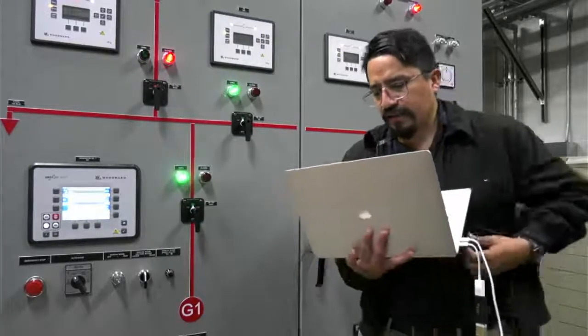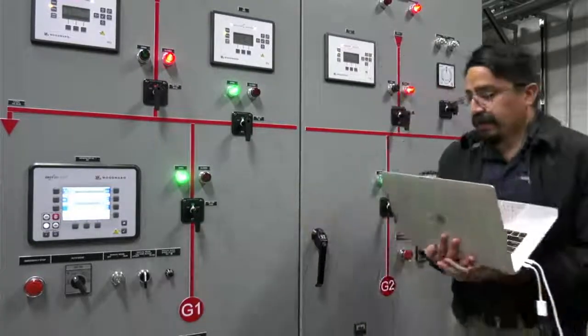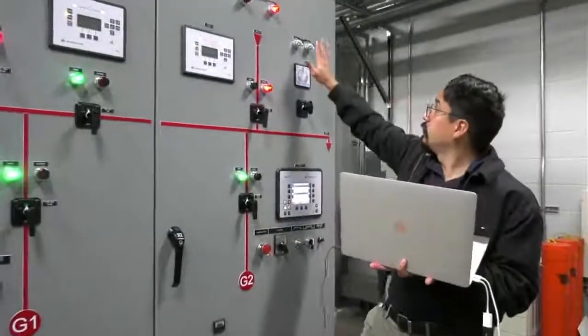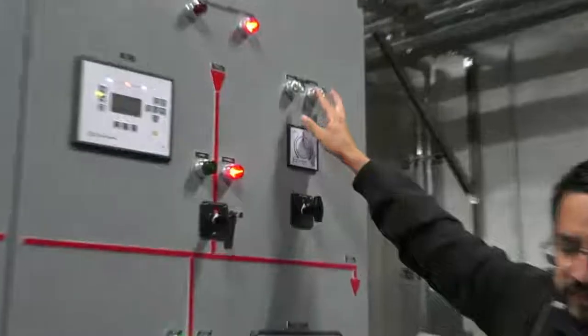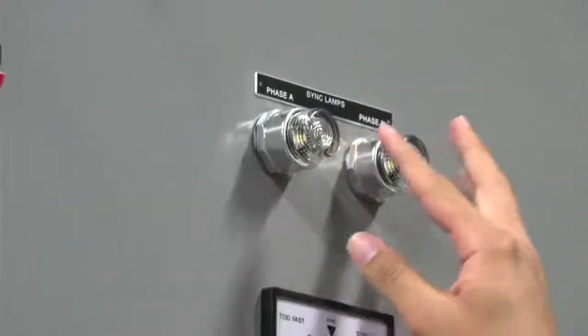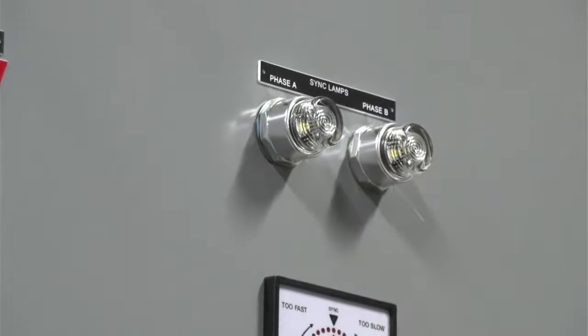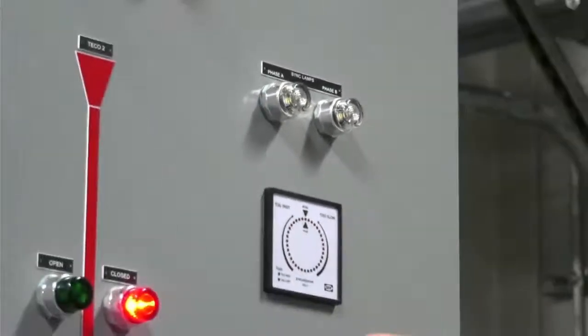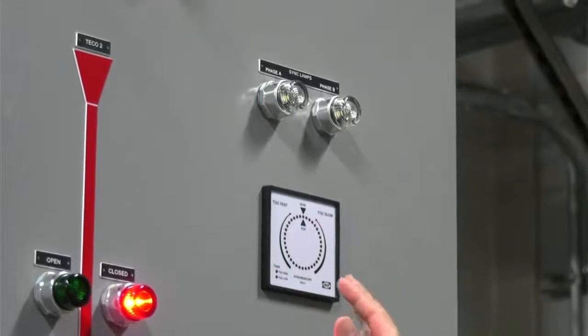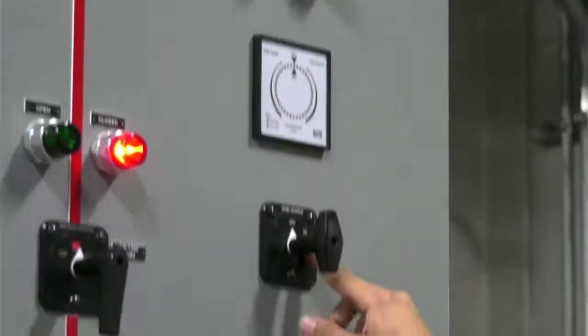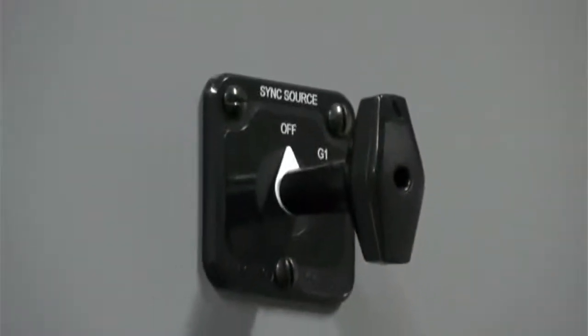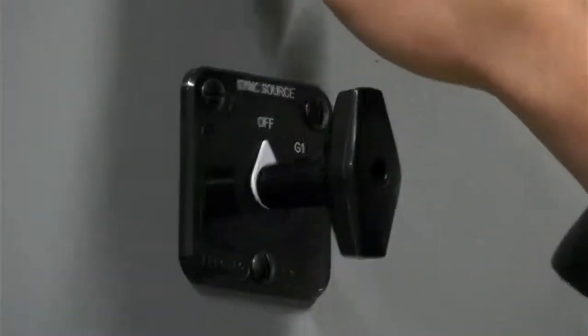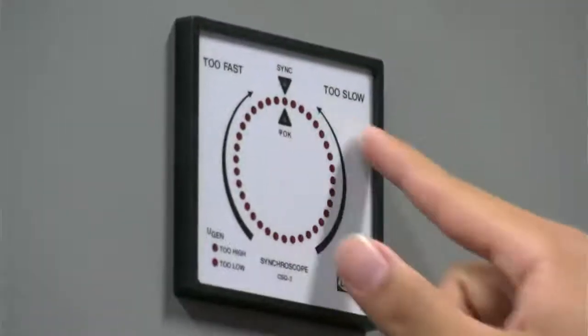So group number 7 on sheet 34 is about these components right here. Synchronizing lamps, the synchroscope, and the sync source. This is being used when the system is in manual and you want to synchronize the generator against the bus bar. So when you do that, basically you select which one is going to be synchronizing, and then close it manually when the synchro indicates you can do so.